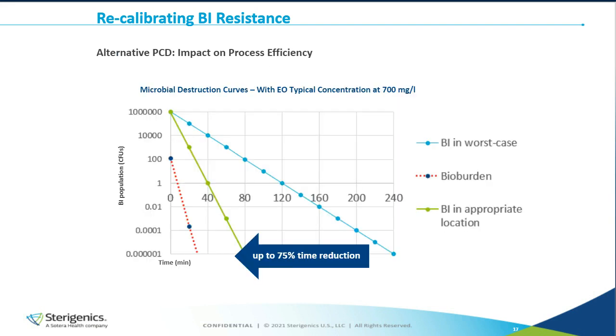And with this example, we have been able to reduce the duration of the cycle without changing the concentration by 75%. So it means that we could have a quarter of a cycle being able to reach the 10-6 SAL that we were targeting for. So it means that we still have margin compared to natural bioburden, but we could reduce significantly the amount of exposure time that was required.